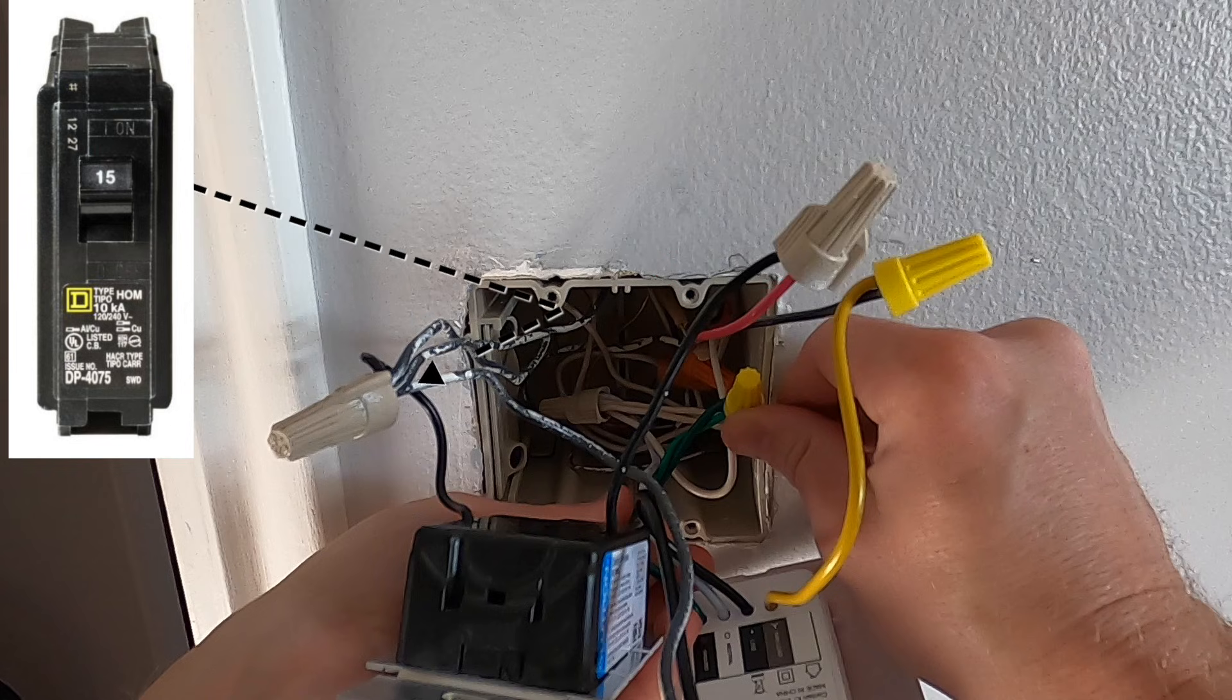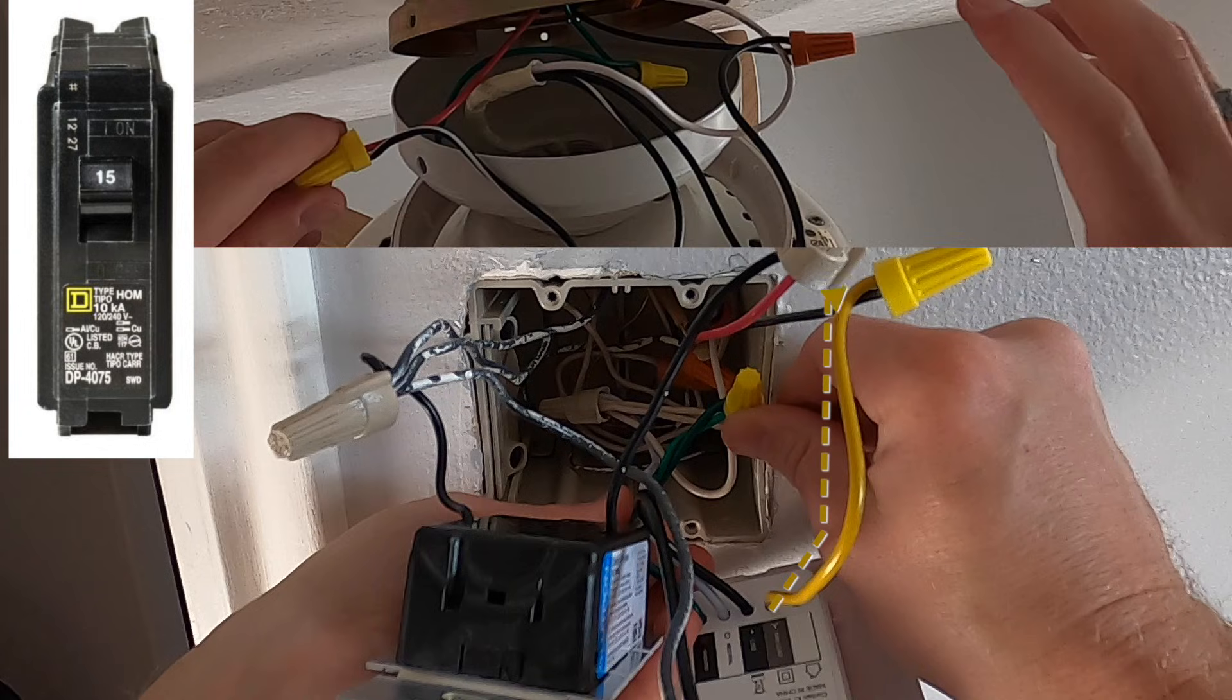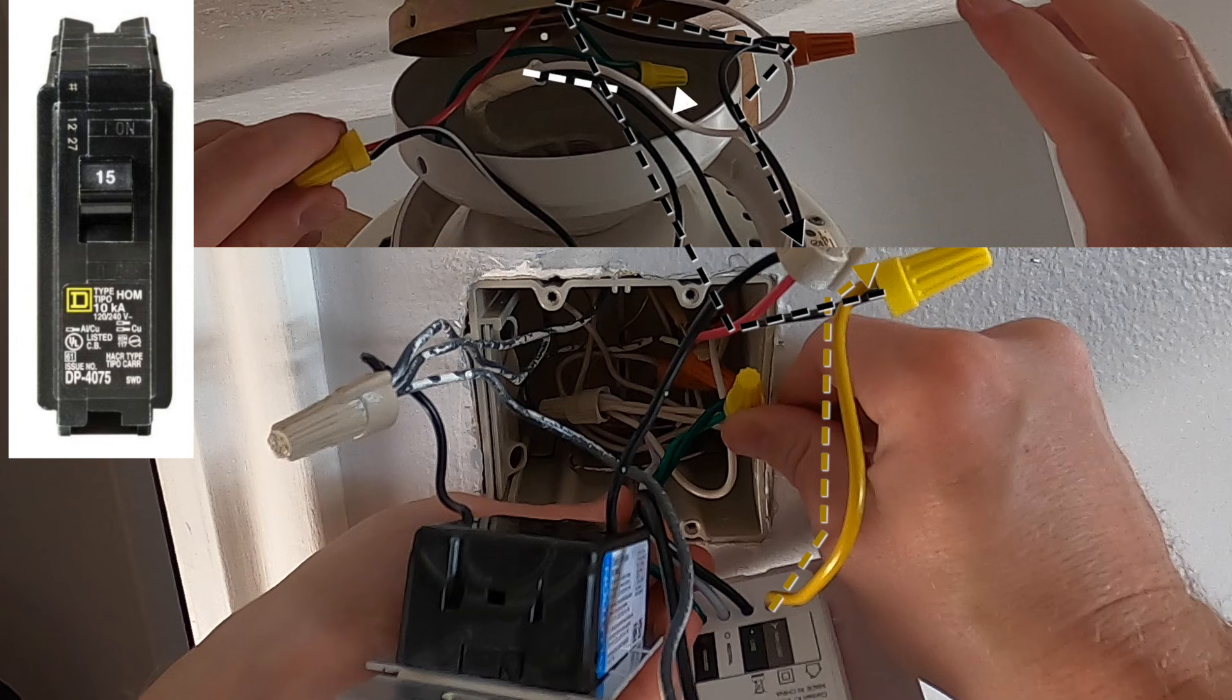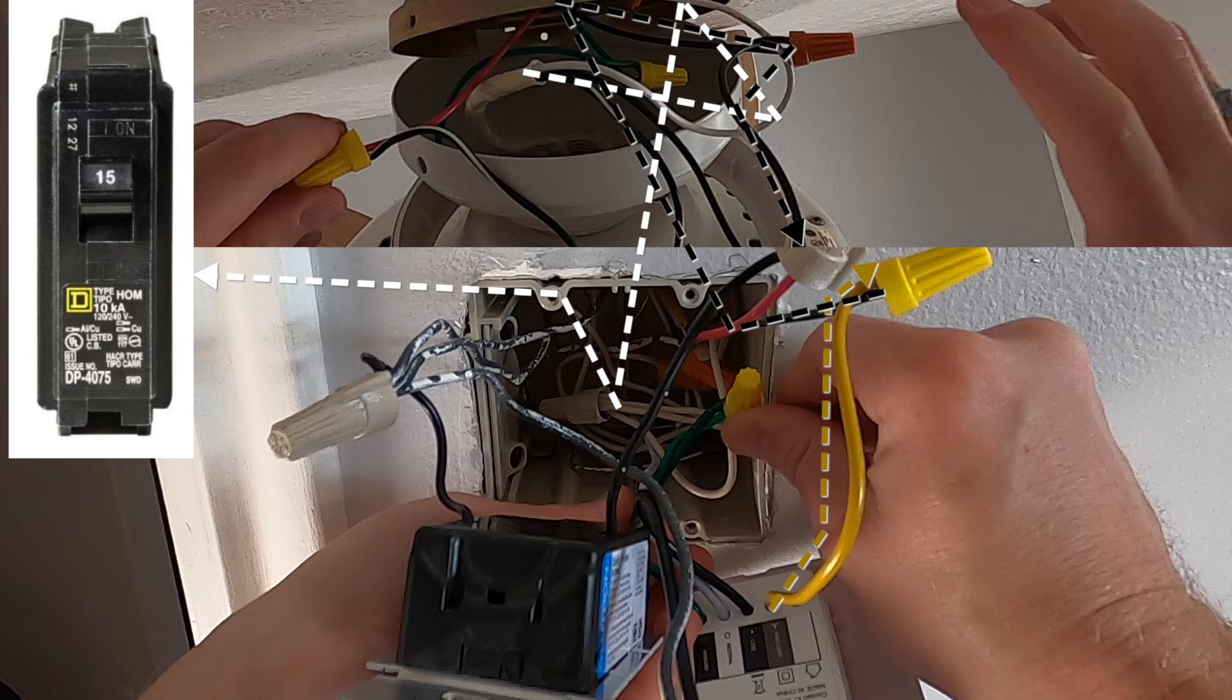For the fan switch, it gets power from the circuit breaker. When the switch is turned on, it sends power through the yellow wire into the black wire to control only the fan. Then the white neutral wire comes back from your fan back into the switch box and back to the circuit breaker panel to complete the circuit.